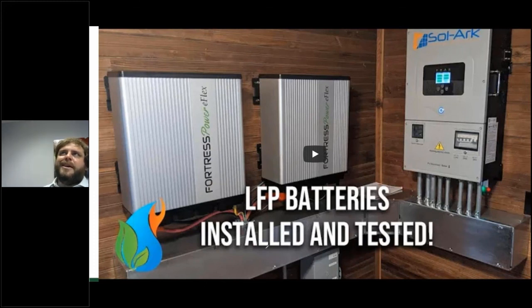We've had a few hundred eflexes installed in the last couple of months, and we've had one blown fuse that occurred on the DC side of a charge controller wiring that carried all the way into the battery. The takeaway was, first off, we had to ship the installer a specialty fuse, because you just can't go and buy the fuse inside our eflex off the shelf. And then they had to take this cap off and put the fuse into the battery. It's not an impossible thing to do, but it would have been a lot easier to have an external fuse inside the raceway that they could have installed.